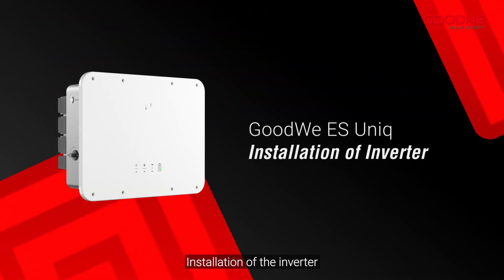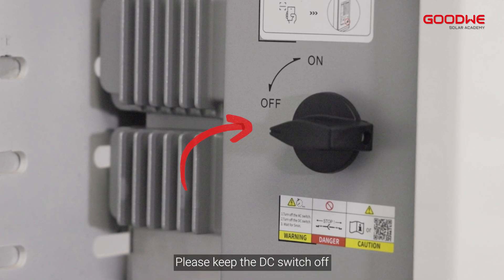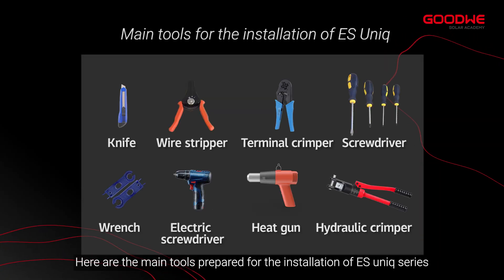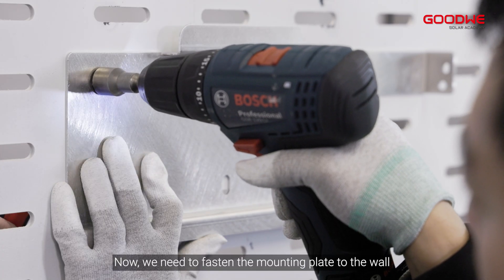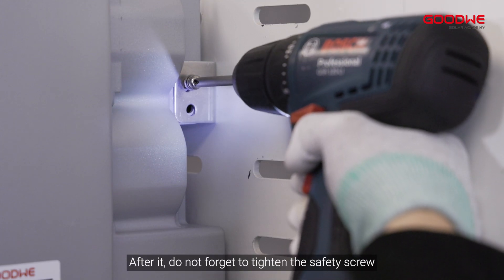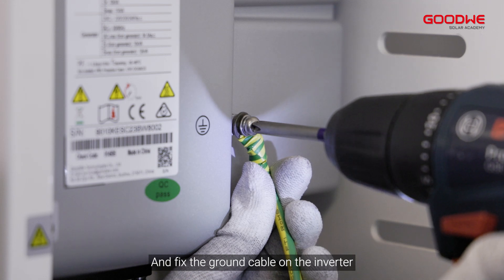Installation of the inverter — before doing any further process, please keep the DC switch off. Here are the main tools prepared for the installation of the ES Uniq series. Fasten the mounting plate to the wall, then hang the inverter on the mounting bracket. Do not forget to tighten the safety screw and fix the ground cable on the inverter.